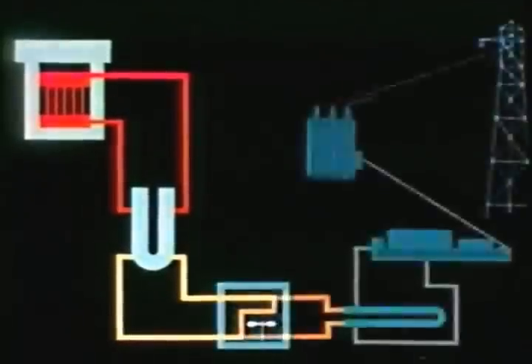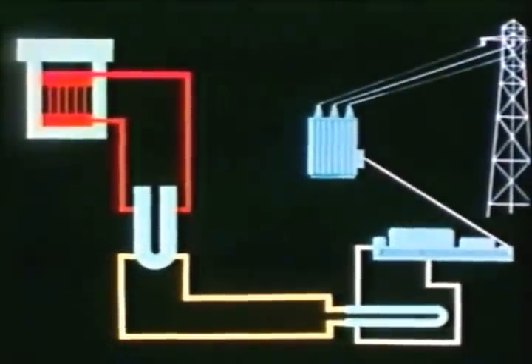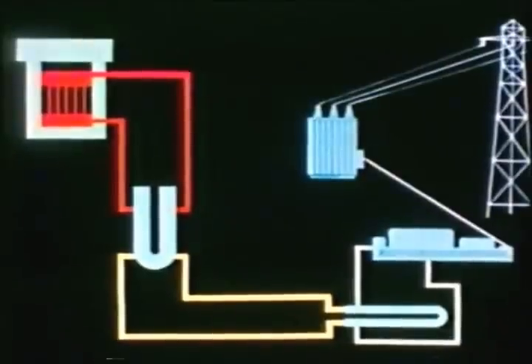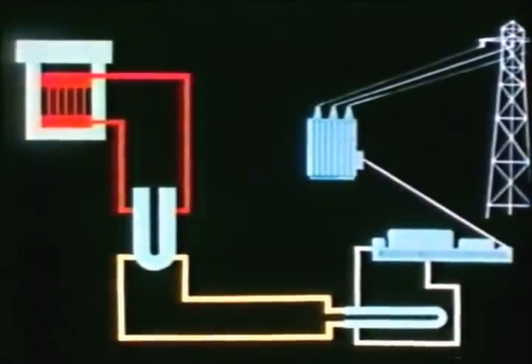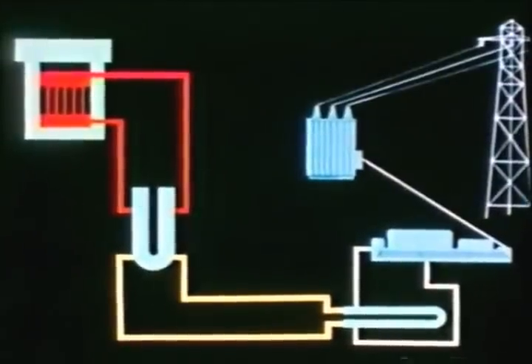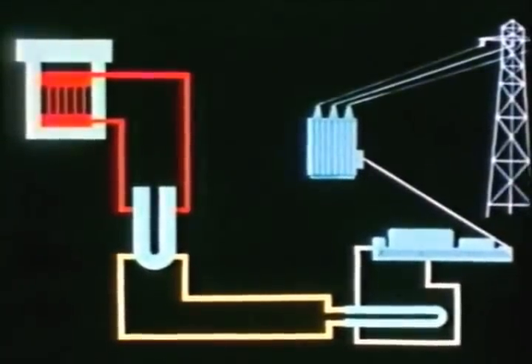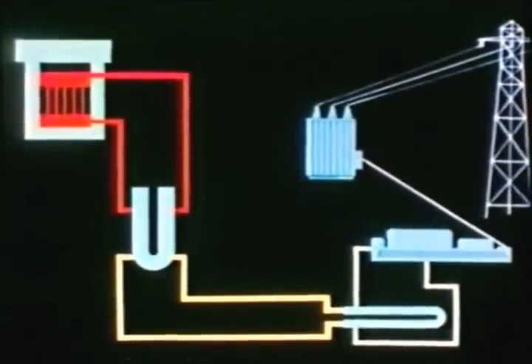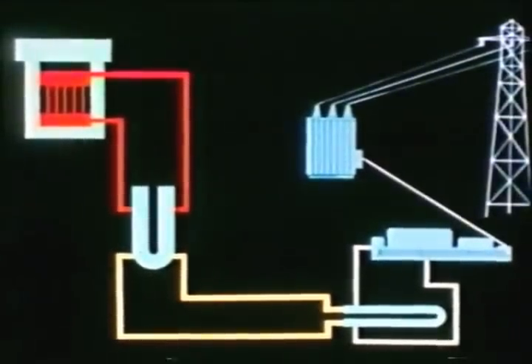The heat from the sodium in the primary loop is transferred by a heat exchanger to a secondary loop, which is non-radioactive. The heat from the secondary loop can be exhausted to the atmosphere by an air blast heat exchanger, or it can be utilized in a steam generator. The steam drives a conventional turbine generator for the production of electricity. The steam plant can produce 6,500 electrical kilowatts, with the reactor operating at its design power level of 20,000 thermal kilowatts.